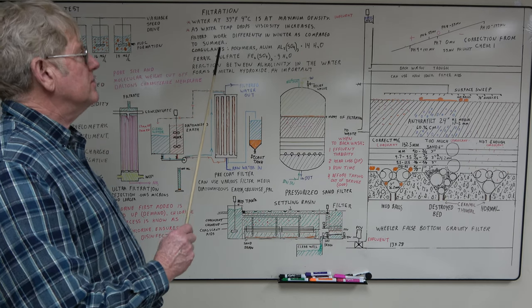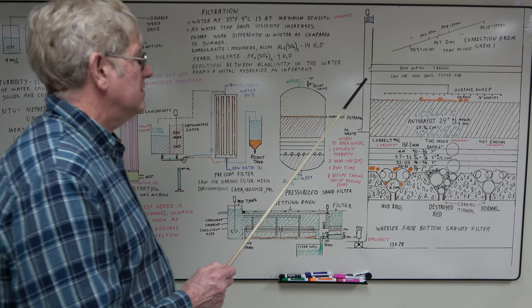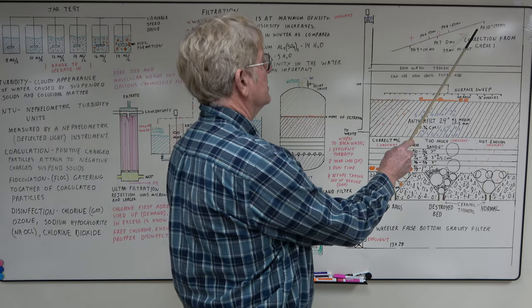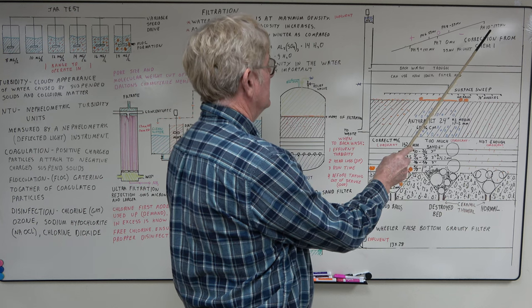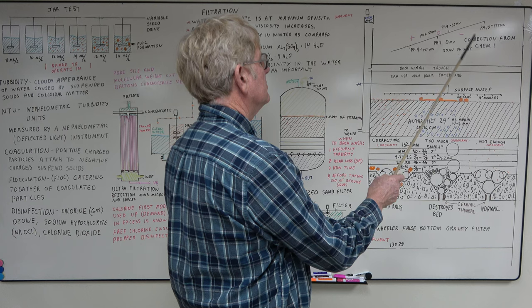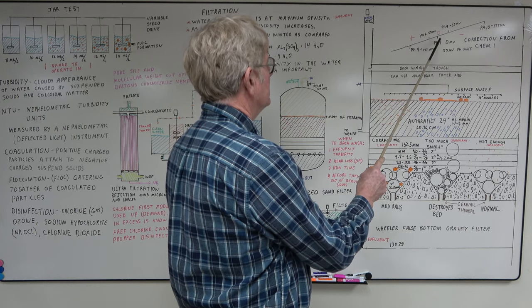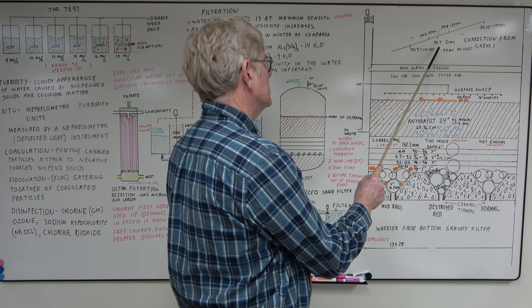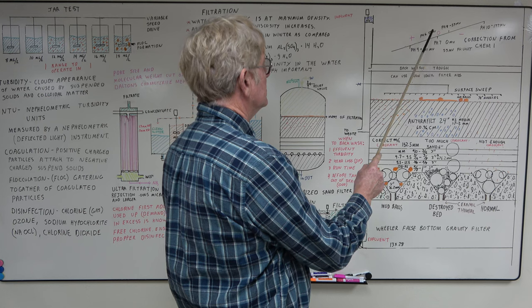Okay, this is our filtration video. We had a little error on our Chemistry 1 video. We left off the minus on the pH 10. It should be minus 177 millivolts at a 59 millivolt per pH unit slope. pH of 7 has zero millivolts. The hydrogen ions inside the electrode are the same as outside, so there's no electrode potential.